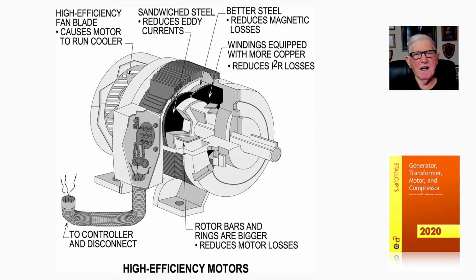To the left, it has a high efficiency fan blade that causes the motor to run a lot cooler. It's sandwiched steel to reduce the eddy currents big time. Better steel reduces the magnetic losses. And windings equipped with more copper give the motor more power, and it reduces the I squared R losses. The rotor bars and rings are bigger, which reduces motor losses. And of course you see the pigtail here going to the controller and the disconnecting means.